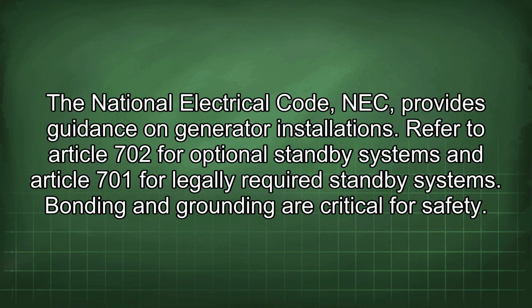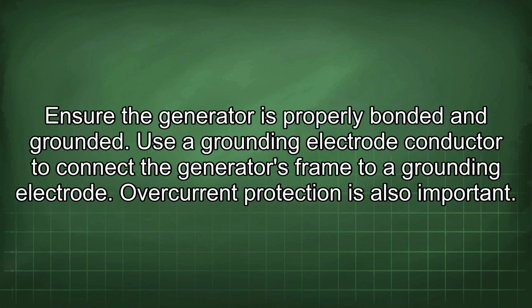The National Electrical Code, NEC, provides guidance on generator installations. Refer to Article 702 for optional standby systems and Article 701 for legally required standby systems. Bonding and grounding are critical for safety. Ensure the generator is properly bonded and grounded. Use a grounding electrode conductor to connect the generator's frame to a grounding electrode.